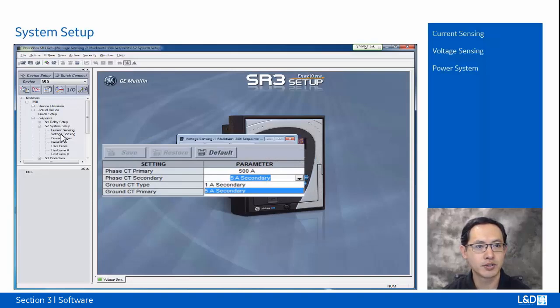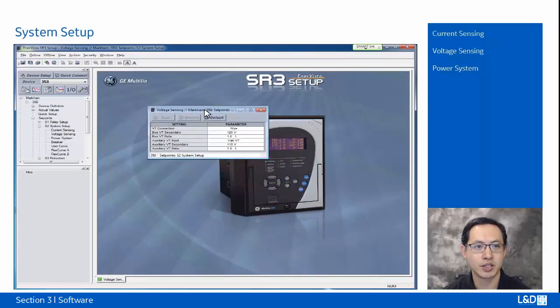Under the voltage sensing, we can set up the VT connection, Y or delta. We can set up the bus VT secondary and ratio, and the auxiliary VT input secondary and ratio. The VT secondary should be the secondary nominal voltage. It needs to be line to line for the delta and line to neutral for the Y connection.